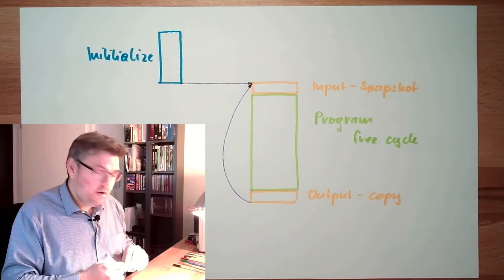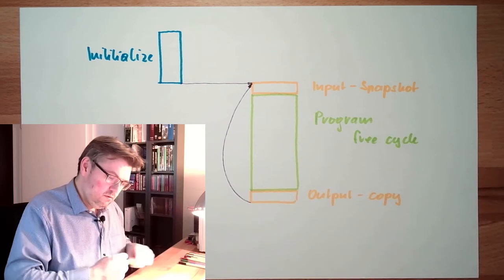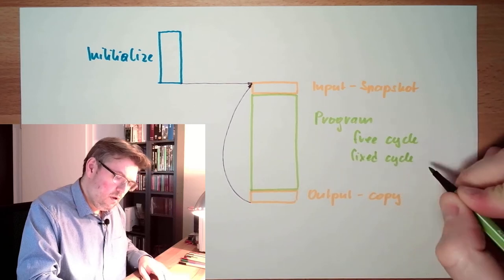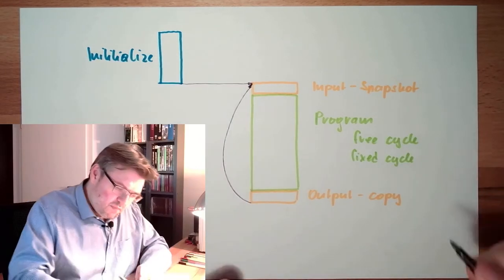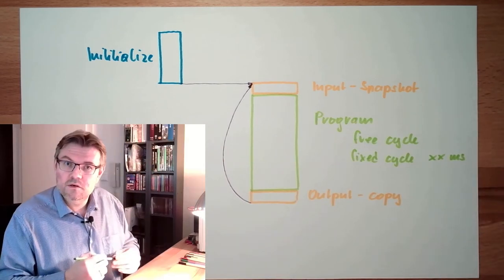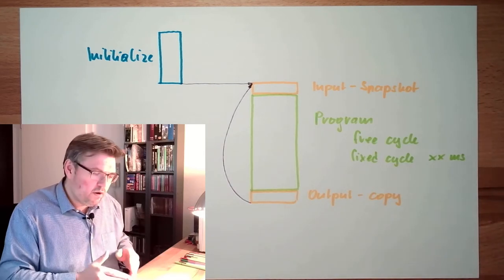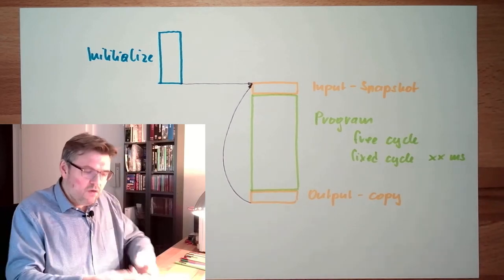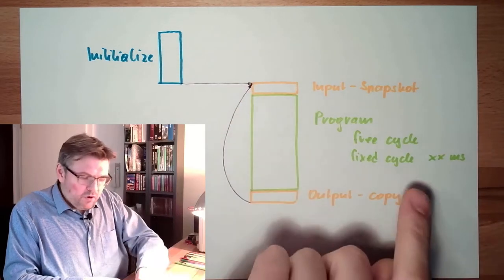However, there are also the possibilities of fixed cycle. In a fixed cycle program, the program will start to be executed after XX milliseconds. I can adjust this usually, or I have to select - there are different fixed cycles. One is starting every 10 milliseconds, one is starting every 20 milliseconds, one is starting every 100 milliseconds and so on. I use a fixed cycle when I'm sure this program is executed every whatever milliseconds.